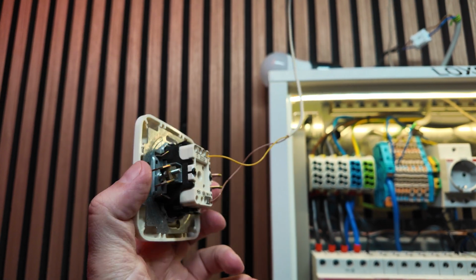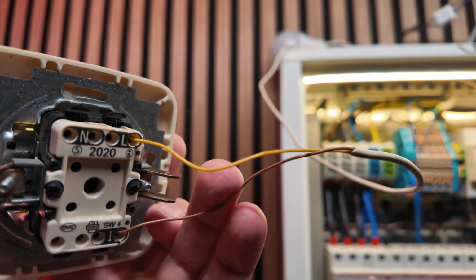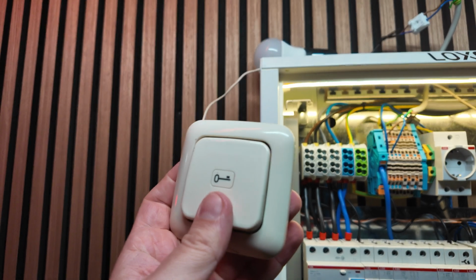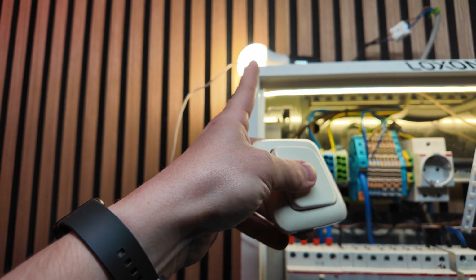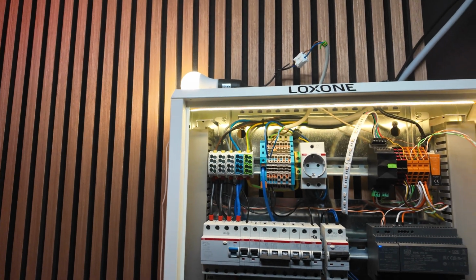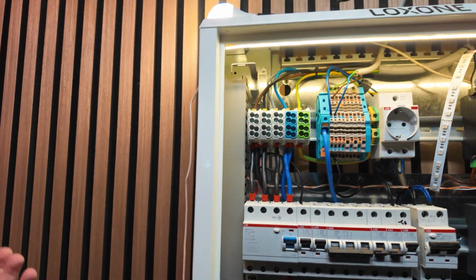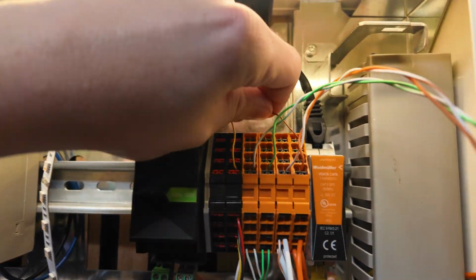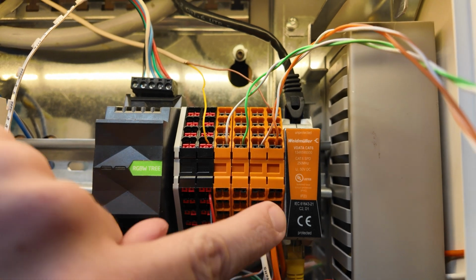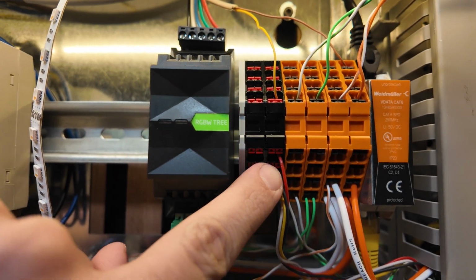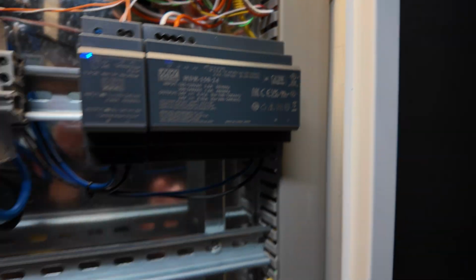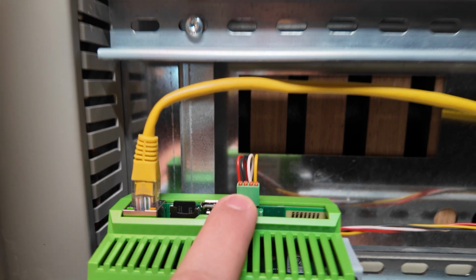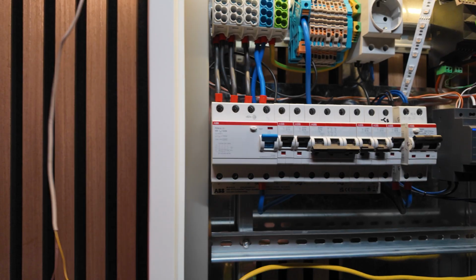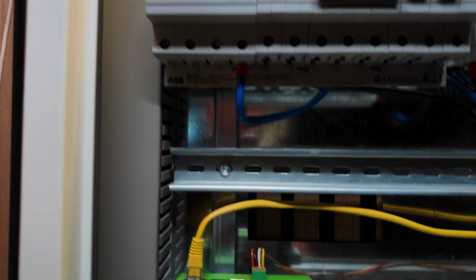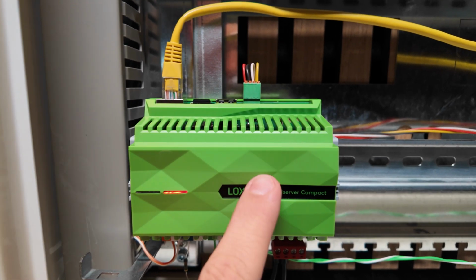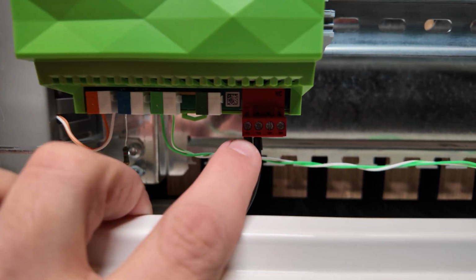Let's now say we would like to use one digital input for the super simple push button here. We need two wires, 24 volt coming, and then once I press the button, the light should go on. It's a 230 volt line on this breaker here. How would I do this? Typically, not at all, because I'm using the Loxone push buttons in the bus topology. But just for this example, I'm using once here the 24 volt of this clamp, and then I'm going back to this first digital input. So these four cables here go all the way down to the mini server's four digital inputs. And the first one, I think, was the red one. Yes, that's correct. So once I press the button, the mini server receives the 24 volt signal, and the logic I programmed in the Loxone free basic training is then turning on the lamp, which closes the first relay.